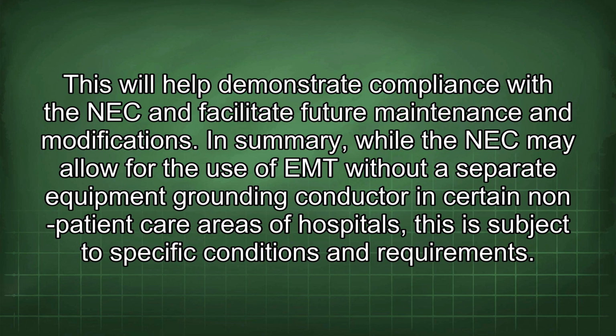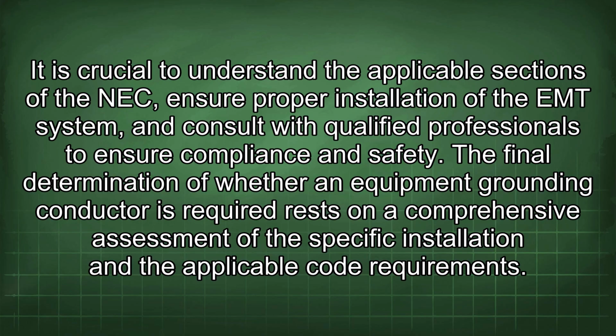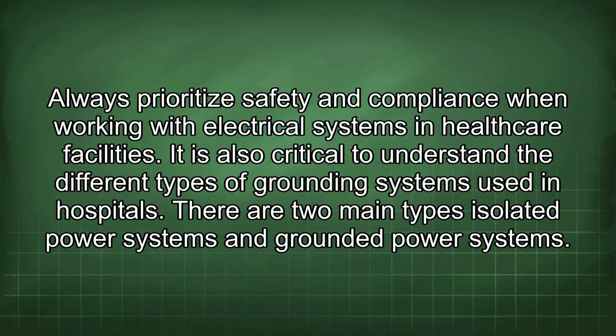In summary, while the NEC may allow for the use of EMT without a separate equipment grounding conductor in certain non-patient care areas of hospitals, this is subject to specific conditions and requirements. It is crucial to understand the applicable sections of the NEC, ensure proper installation of the EMT system, and consult with qualified professionals to ensure compliance and safety. The final determination of whether an equipment grounding conductor is required rests on a comprehensive assessment of the specific installation and the applicable code requirements. Always prioritize safety and compliance when working with electrical systems in healthcare facilities.